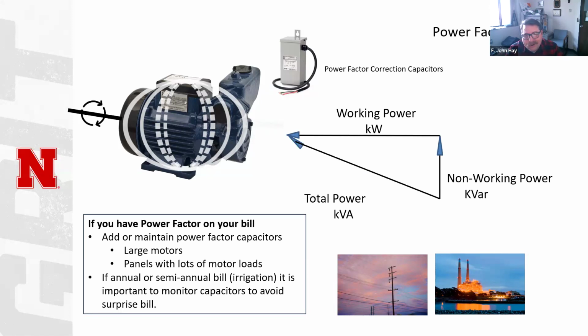The other thing is, and this is a little harder, but I've seen a lot of electric irrigation systems that the motor was oversized and running inefficiently. I can understand how that happens. The motor goes out, the company, you call them up, oh I got this motor sitting on the shelf, we'll put a new one in, but it's oversized. And you got two problems when you oversize a motor. One is it runs much more inefficiently in and of itself. The second is that power factor is best, highest, when the motor is running at full capacity or closer to full capacity. If you're running at partial capacity, your power factor is worse. So you're being double dipped by having inefficient, oversized motors. It's weird to say I have too much power, but I have a motor that's oversized. That's a problem in many irrigation systems.